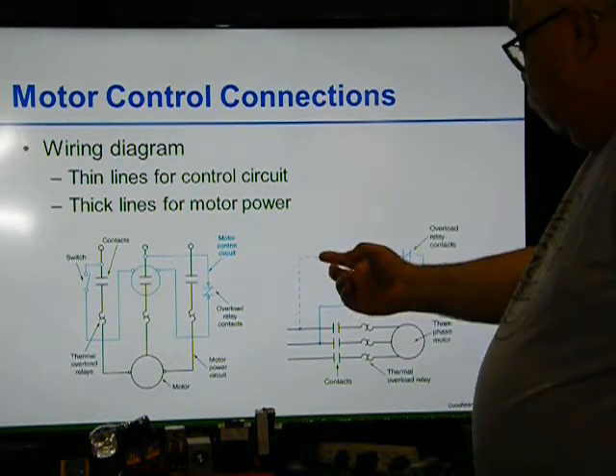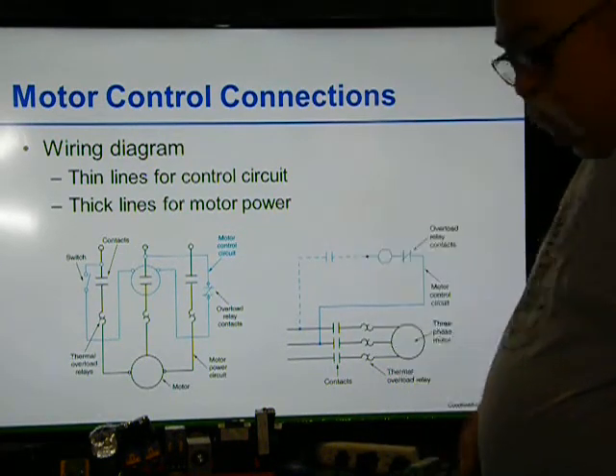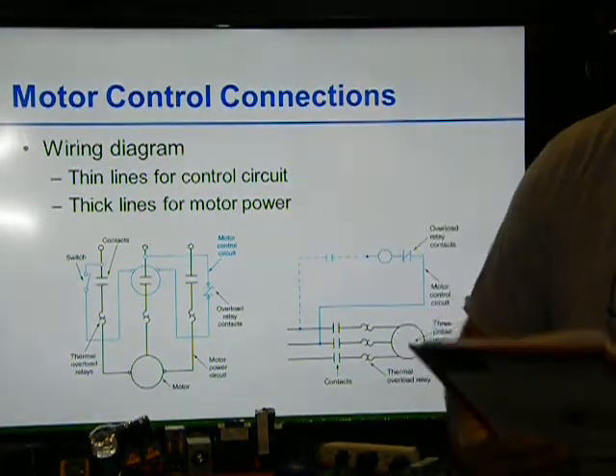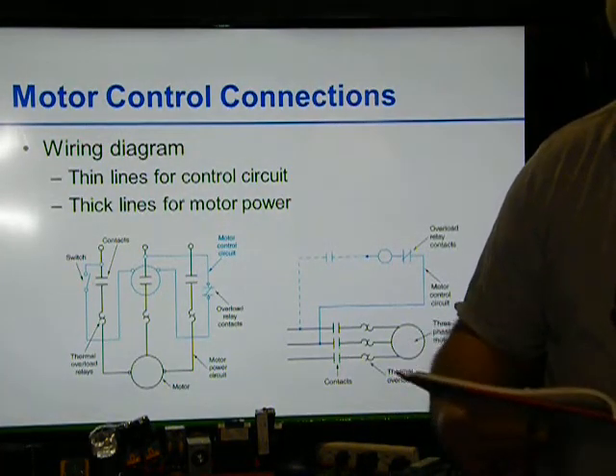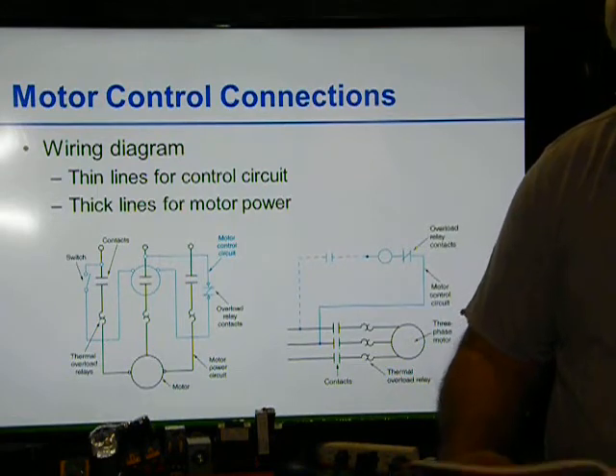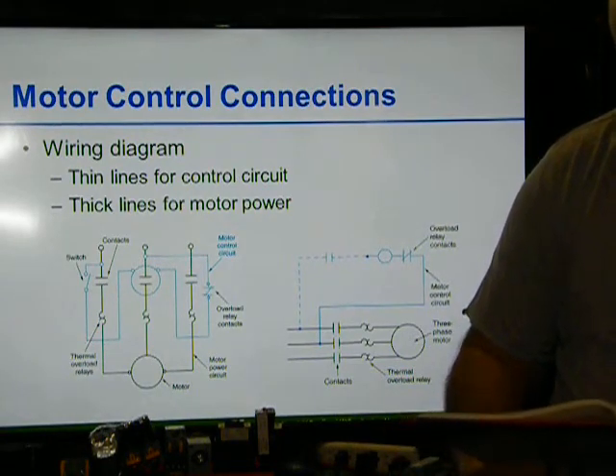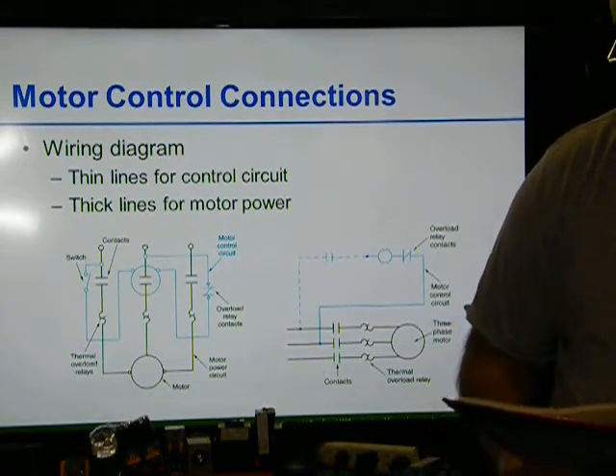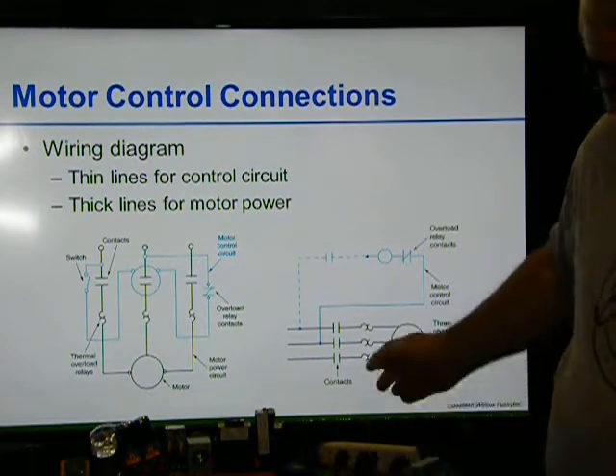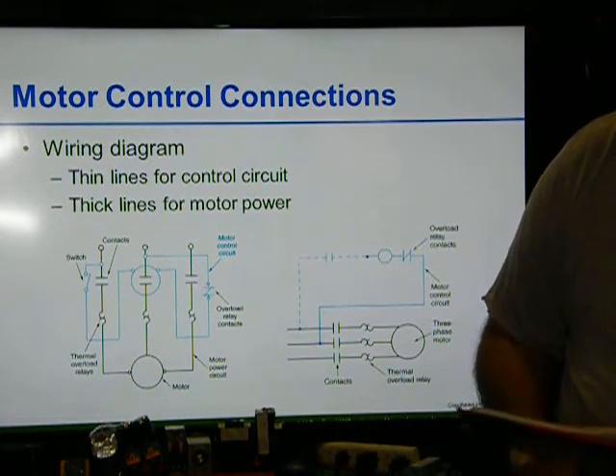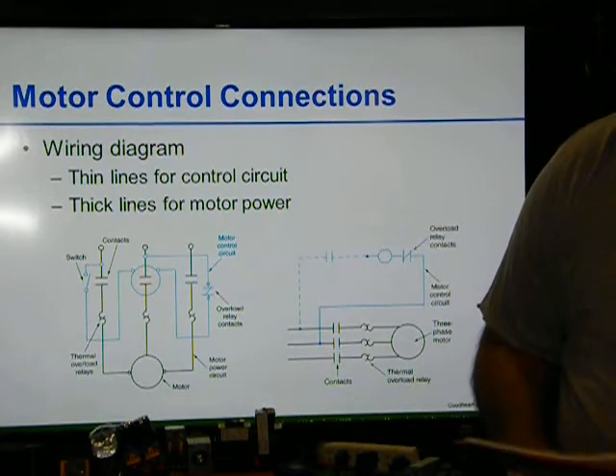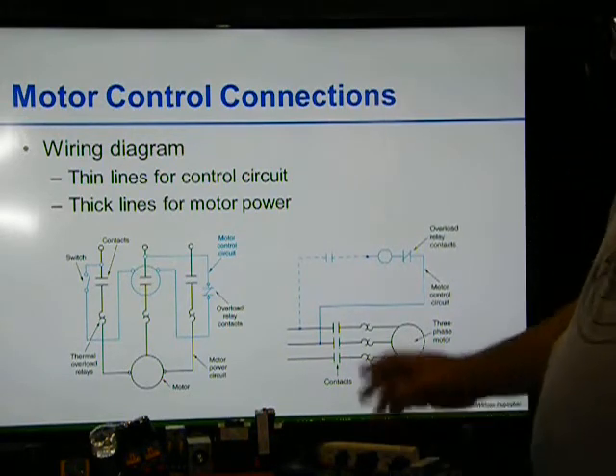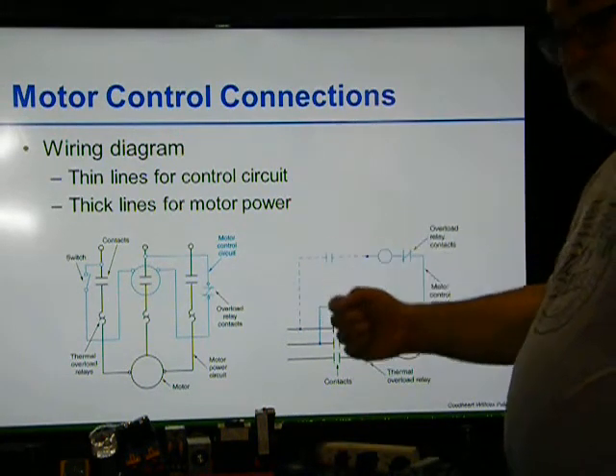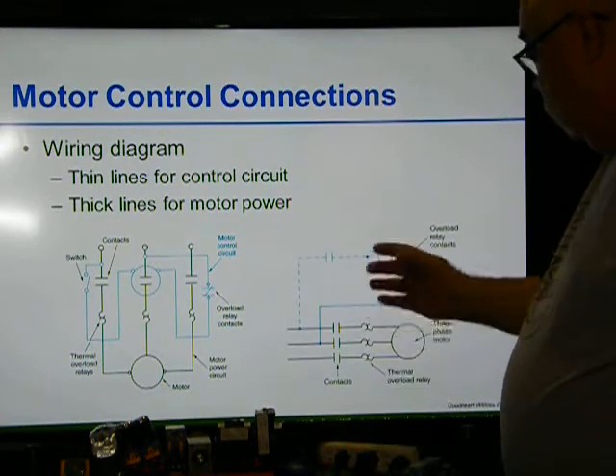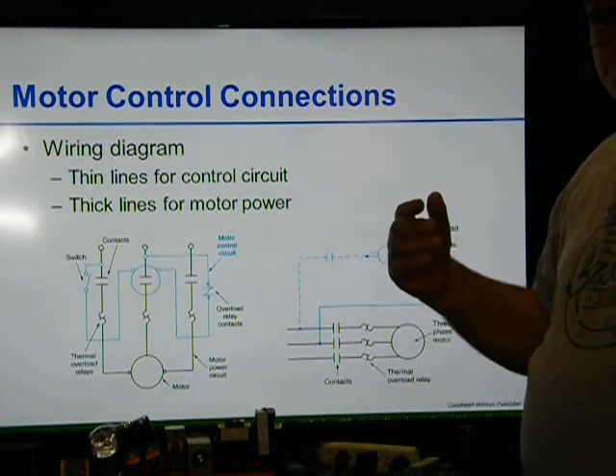The only problem is that once it stays on, if power goes off, we'll get into that a little bit. This is a wiring diagram for the motor control circuit and the power circuit. And the other one here is an elementary drawing of a circuit. This is a 2-wire control circuit. Those are my 2 wires. So this may be a switch. When I turn that switch on, this closes and the motor starts working.